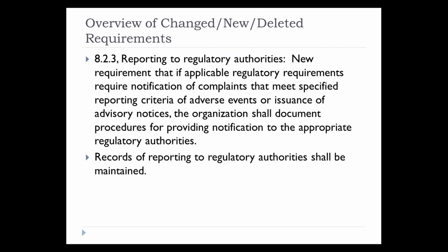8.2.3, reporting to regulatory authorities. This is a new requirement that if applicable regulatory requirements require notification of complaints that meet specified reporting criteria of adverse events or issuance of advisory notices, the organization shall document what their procedure is for providing notification to the appropriate regulatory authorities. So you may never use these procedures, but you have to have them at the ready. What is our process for reporting an adverse event or issuing an advisory notice? Records of reporting to regulatory authorities need to be maintained.